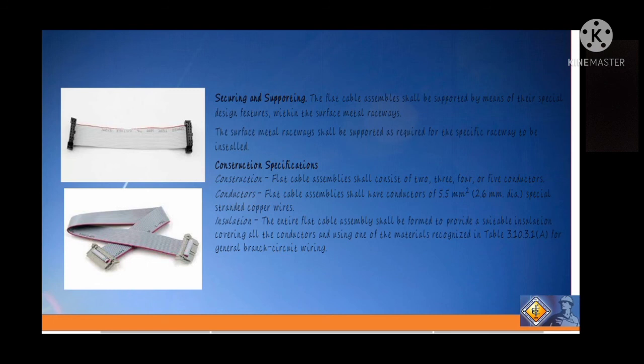So for securing and supporting naman, the flat cable assembly shall be supported by means of the special design features within the surface metal raceway. So the surface metal raceway shall be supported as required for the specific raceway to be installed. So in terms of construction specification, the flat cable assembly shall consist of 2, 3, 4, or 5 conductors.